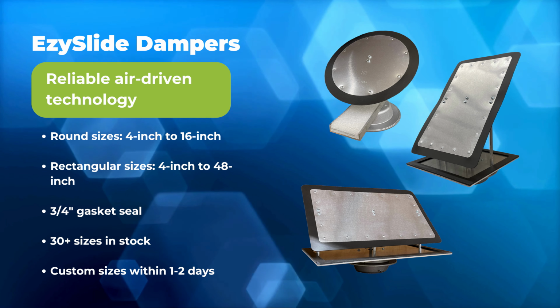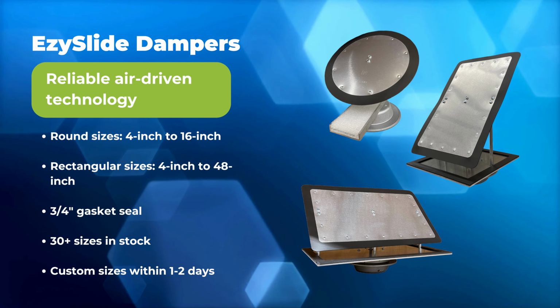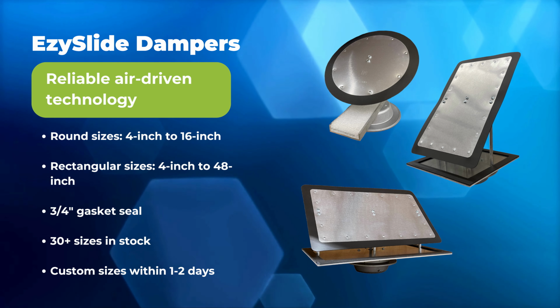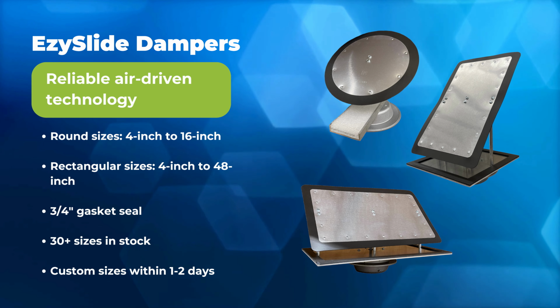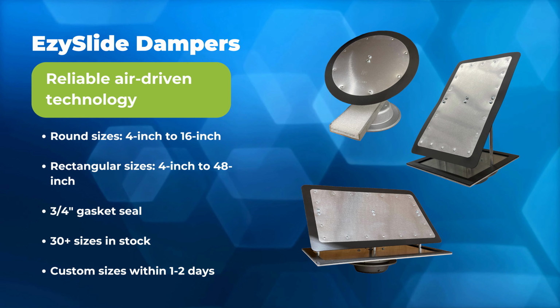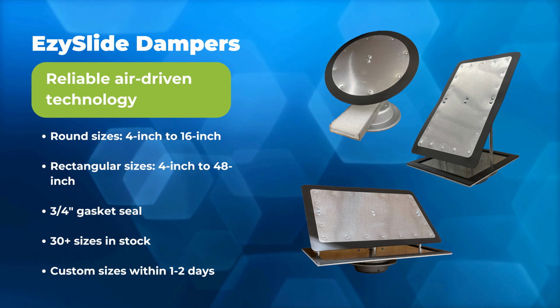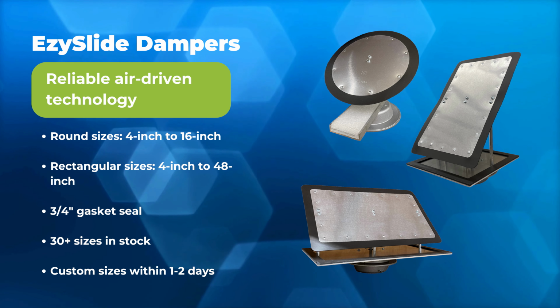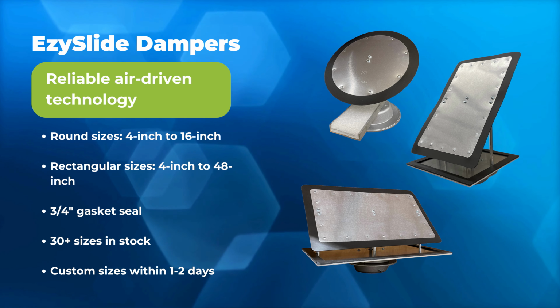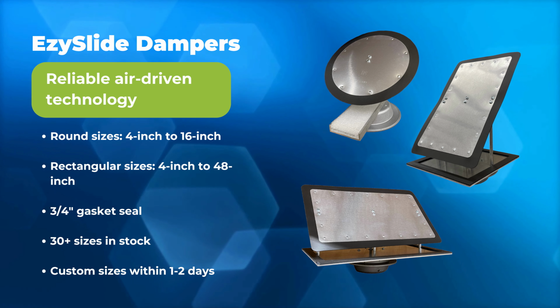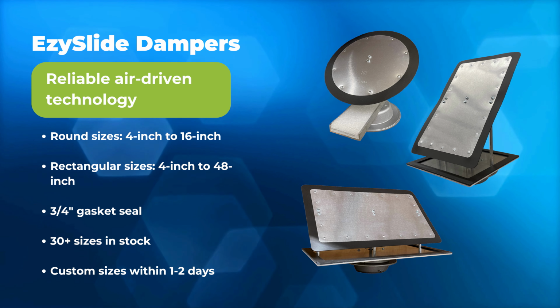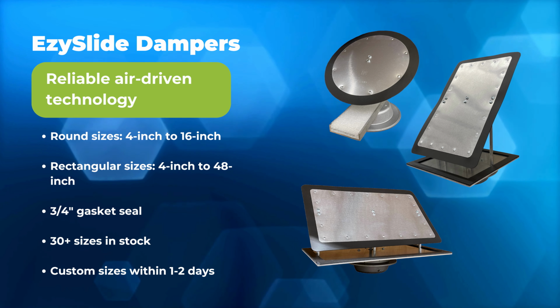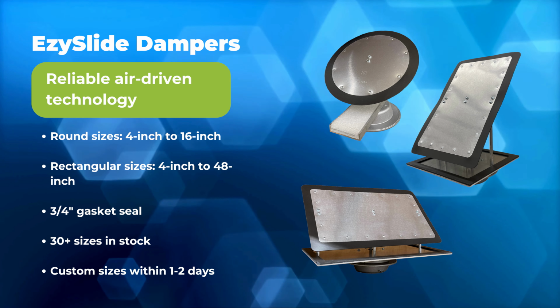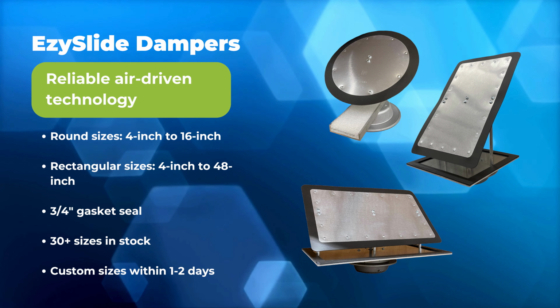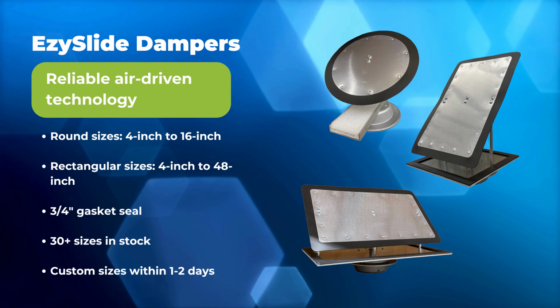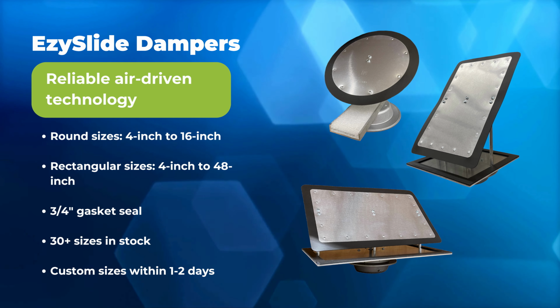And then all of our dampers are going to have a 3/4 inch gasketed seal around the blade itself. So it's going to be a 100% seal when the damper closes, so you get no bleed by on the dampers themselves. And then we do offer a lot of custom sizes as well. If you have a custom size that needs to be ordered, you can call your local distributor. Usually, as long as we get it early enough in the day, it'll ship out that same day or early next morning. But typically within 24 hours, we'll get any custom size damper out to you guys. So there's no real waiting around or lead times with that.